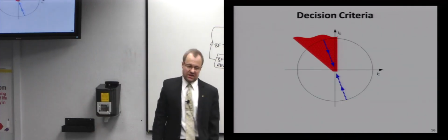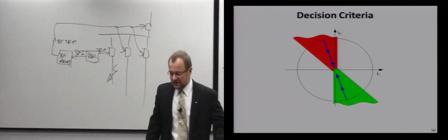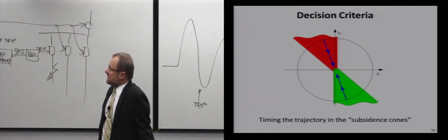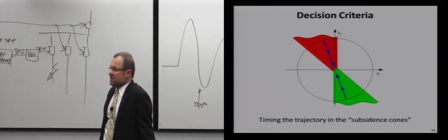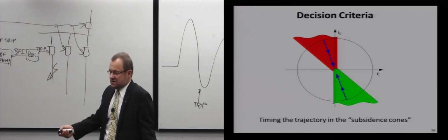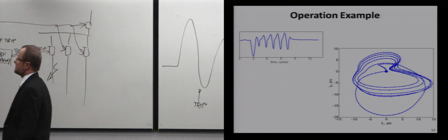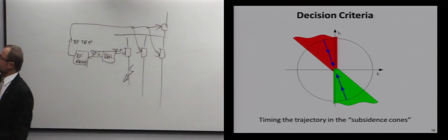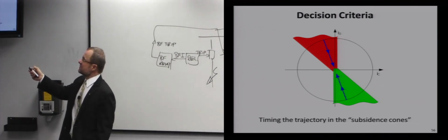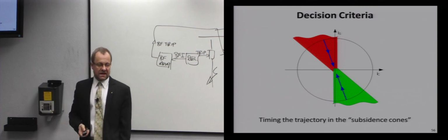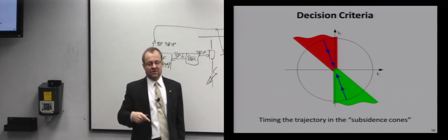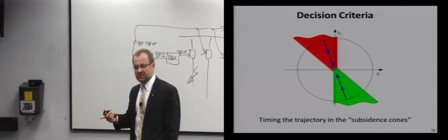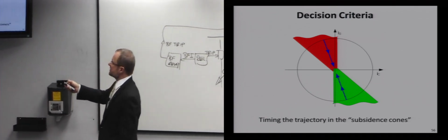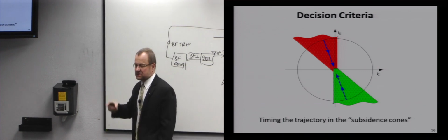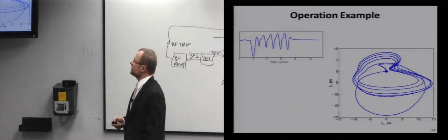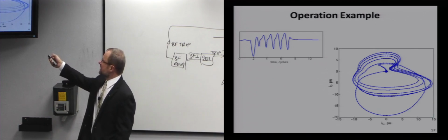So what I will do is I will shape two cones. They are simple comparators. And I will run a timer checking how long I am within a cone. To shape a cone is just a linear calculation on the signals that I measure, right? So when I have a fault, I keep flying through those cones. So I enter, I start the timer. Before the timer expires, I am out. And I could pretty accurately estimate the worst time, how long I'm going to spend within that cone. It's going to be a few milliseconds. So I am in and out because I'm constantly driven by the AC source, because the fault current is there. At the moment the fault current is removed, I stop flying in and out and I reset this way.